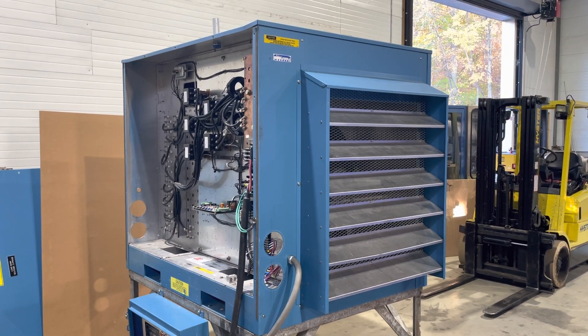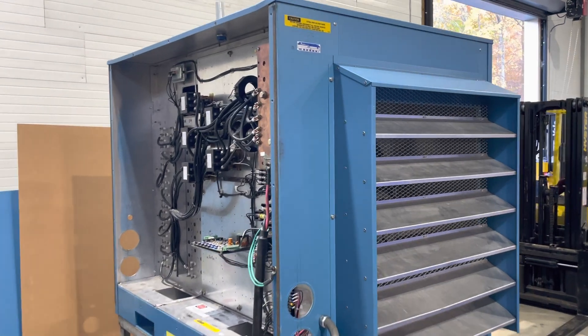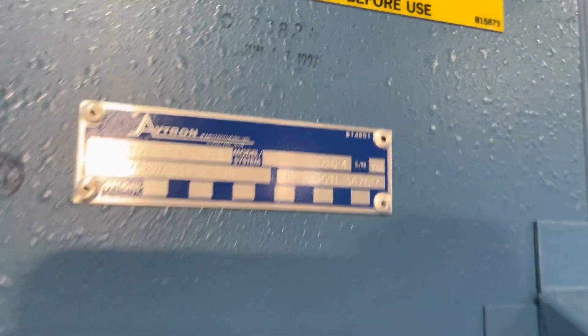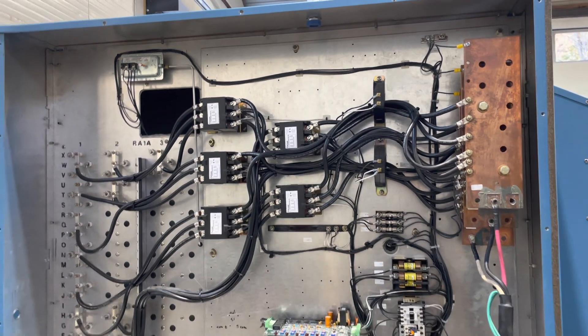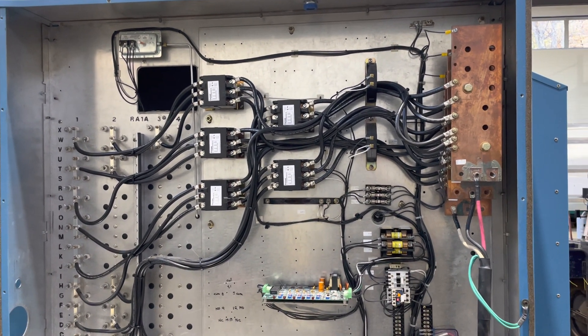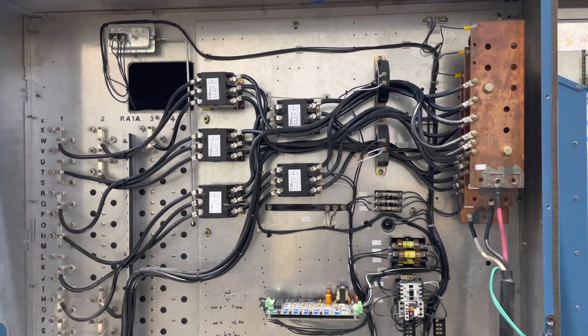Here we have an Avtron K695 load bank. This is set up for 175 kilowatts, and that's done with five contactors, so there's five different load steps, all at 35 kilowatts.